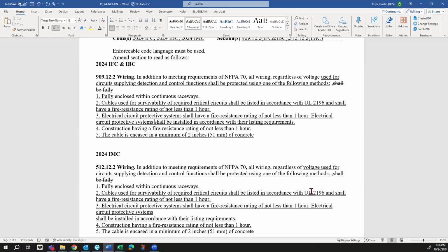It's basically just to provide options for the wiring onto a fire alarm system for detection and control, but not specifically for the ventilation, because other codes adopt that. NEC doesn't have any part that talks about fire alarm that is not associated with a pressurization system. They just say emergency circuits, emergency systems, this is a requirement for it, but it doesn't specify a fire alarm system before you put pressurization in there.